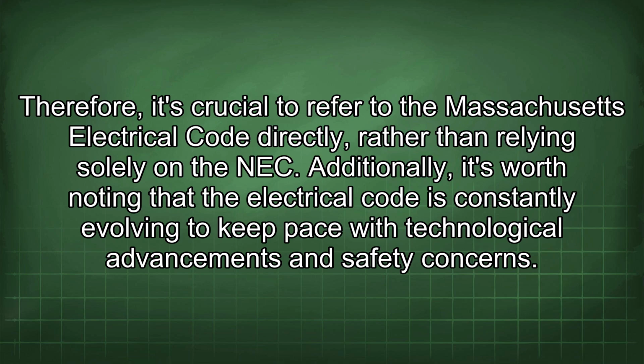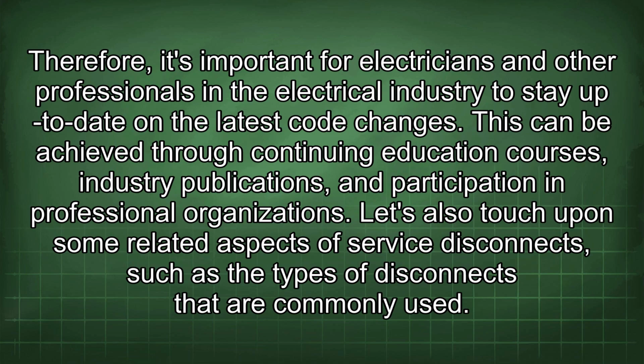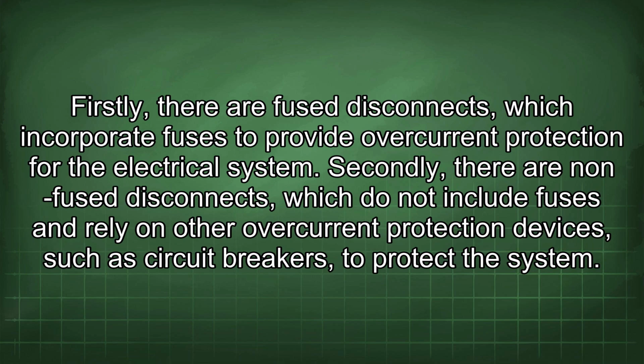Additionally, it's worth noting that the electrical code is constantly evolving to keep pace with technological advancements and safety concerns. Therefore, it's important for electricians and other professionals in the electrical industry to stay up to date on the latest code changes. This can be achieved through continuing education courses, industry publications, and participation in professional organizations. Let's also touch upon some related aspects of service disconnects, such as the types of disconnects that are commonly used. Firstly, there are fused disconnects, which incorporate fuses to provide overcurrent protection for the electrical system. Secondly, there are non-fuse disconnects, which do not include fuses and rely on other overcurrent protection devices, such as circuit breakers, to protect the system.